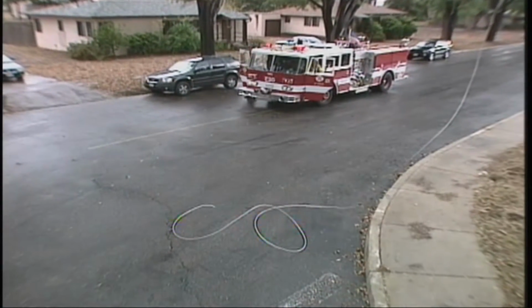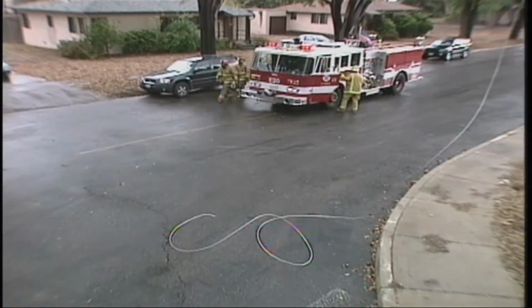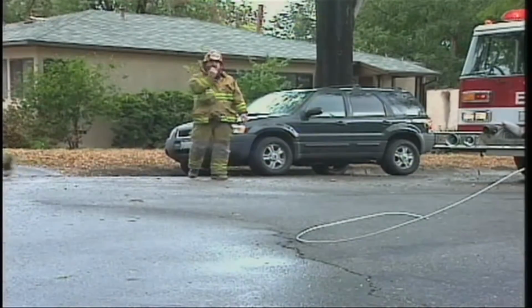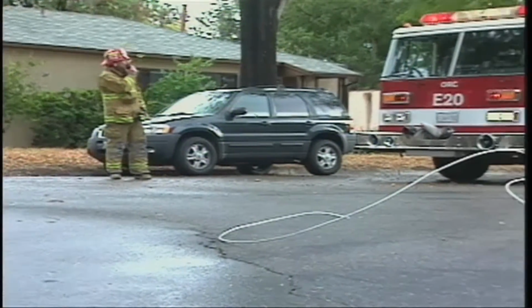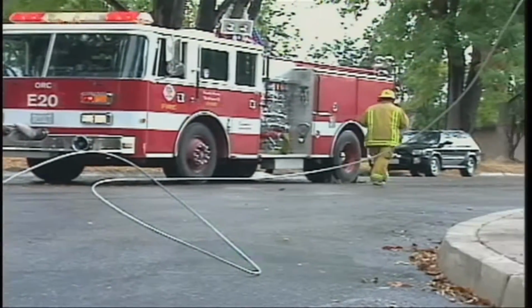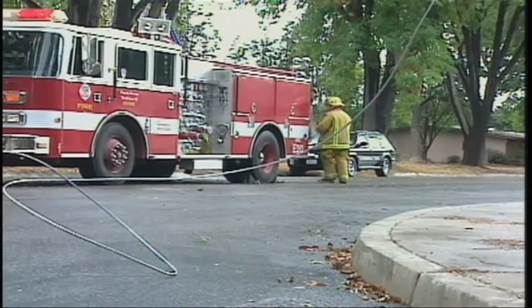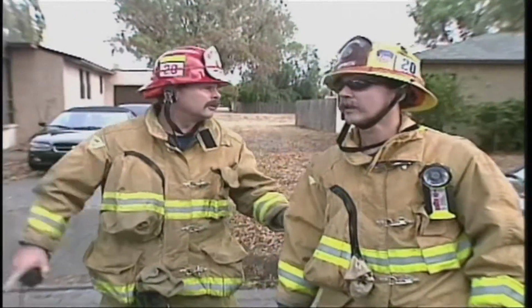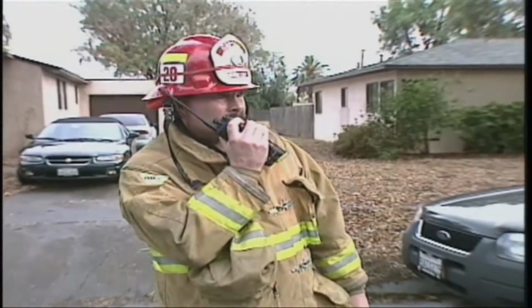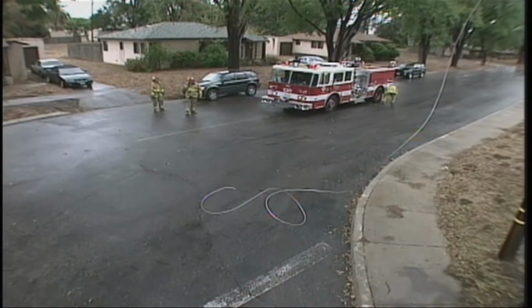It is impossible to determine if a wire is energized by its appearance. While some wires will jump, whip around, curl up, make loud sounds, or emit showers of sparks, others will lie there, silent. Disconnected wires may be live, but not arcing. Also, automatic switching equipment far away from the scene can re-energize wires without notice. Do not attempt to move down wires.